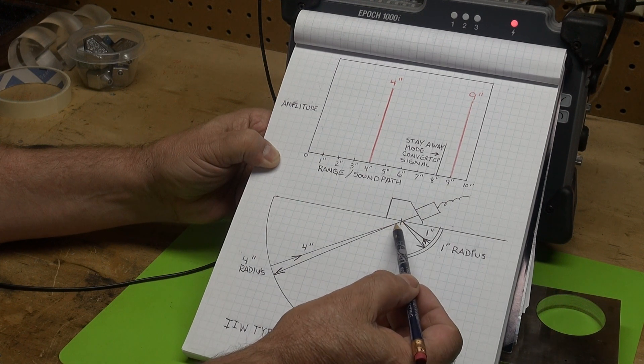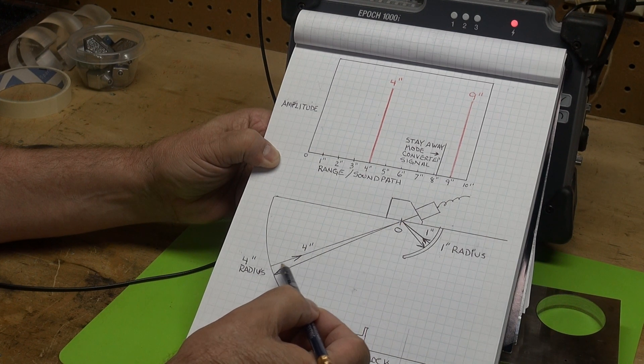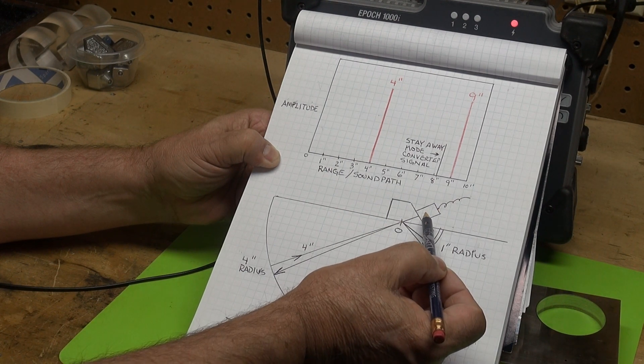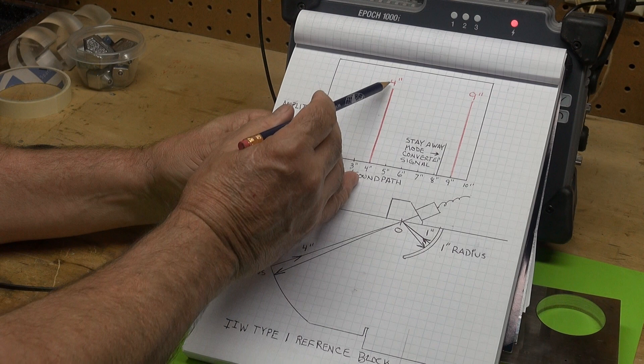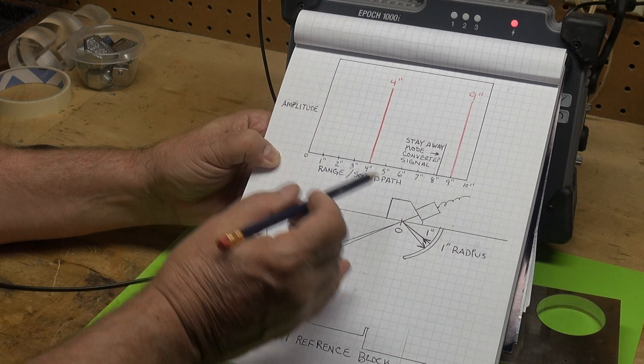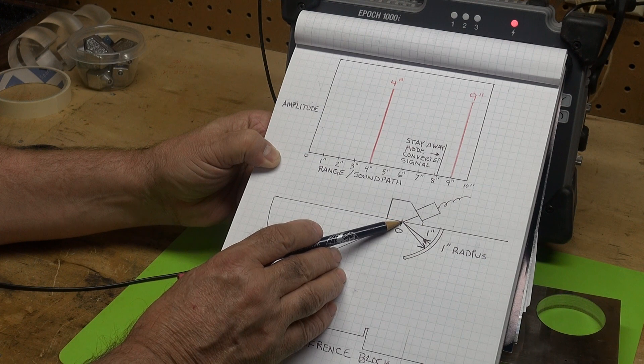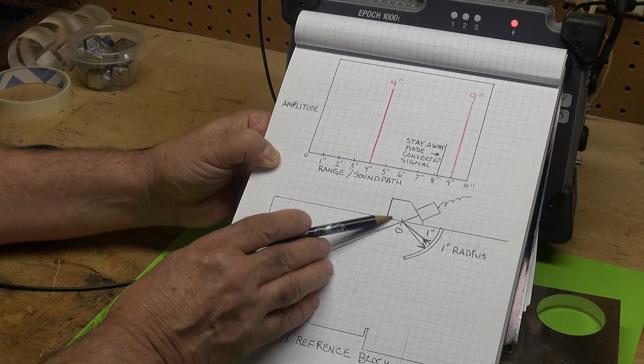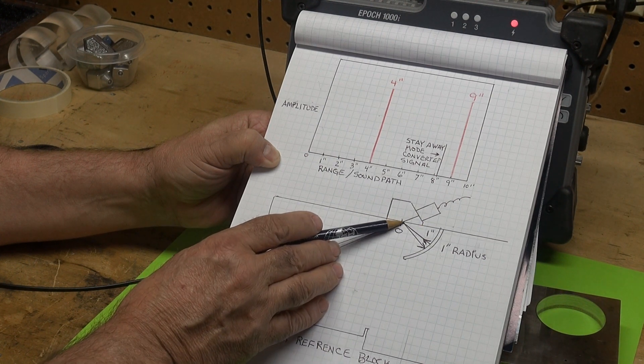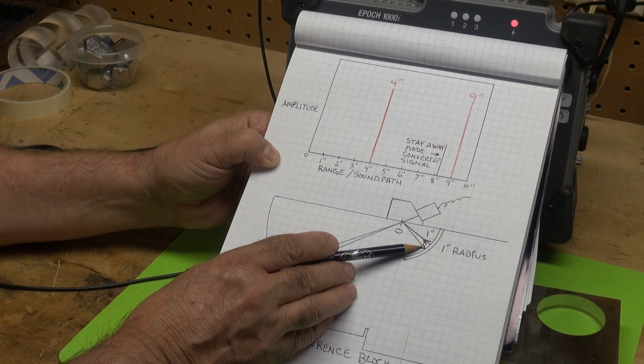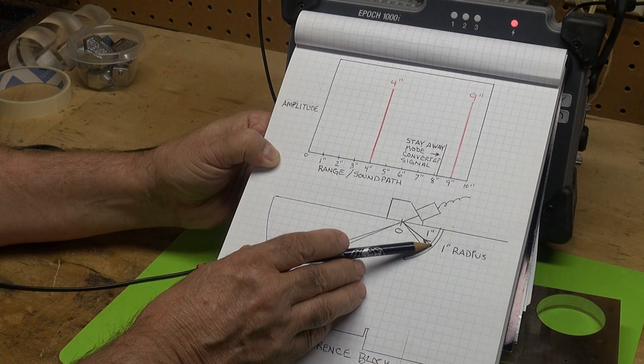So the sound comes out, strikes the 4 inch radius, bounces back perpendicular, strikes our transducer. We get a 4 inch pulse on our display. When that signal comes back it also deflects off the top surface of the block and comes down to strike that 1 inch radius.